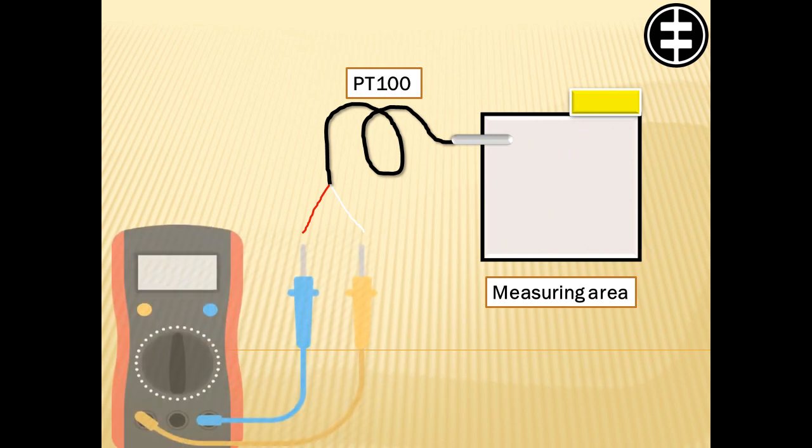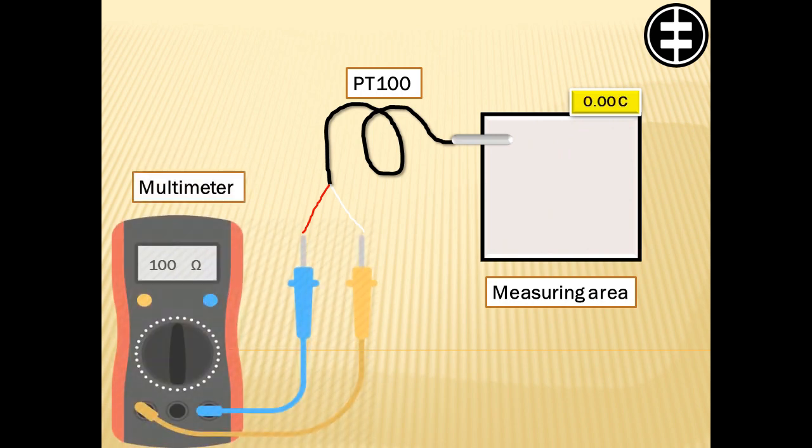Resistance variation is a function of temperature, 0.39 Ohm per 1 degree Celsius. Long term stability is the main difference compared to other temperature measuring methods.